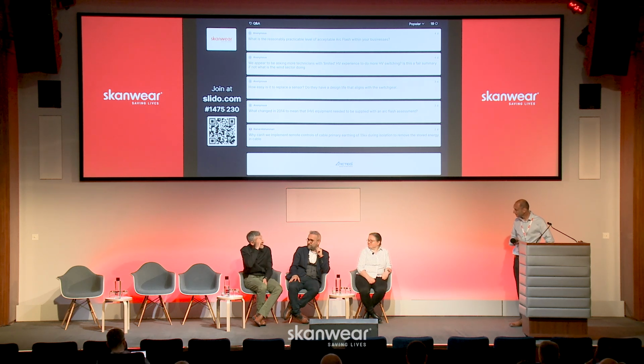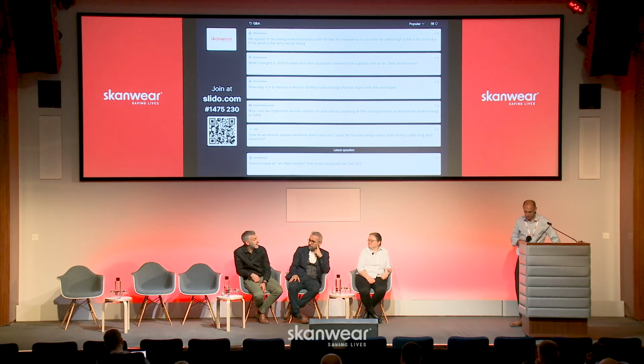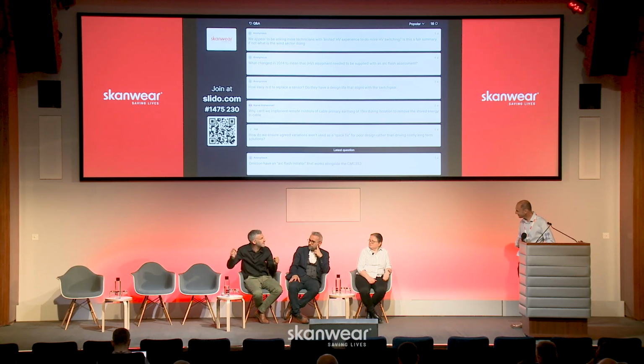So that's an individual company decision. We've specified on design that everything should be 8 cal or below before we'll accept it. If they can't get to 8 cal or below, we have to have some sort of mitigation process or understand the risk for why it can't be achieved. That's actually in our technical requirements when we go to design, so we're trying to design out at the start. And that aligns with our PPE expectations, so they're all linked together.